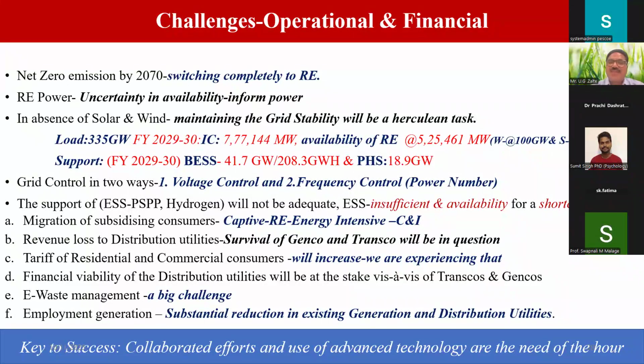So that means 5,000 is the power number, meaning that for every 5,000 megawatt addition or reduction of power, the frequency will be impacted by 1 hertz. If it is more, the frequency will go up by 1 hertz. If it is reduced by 5,000 megawatt, then the frequency will come down by 1 hertz, that is, to 49 hertz. Okay, so this way the grid is normally operated. Okay, voltage control, that is the reactive power control, is meticulously followed to avoid voltage dips and tripping of the lines.